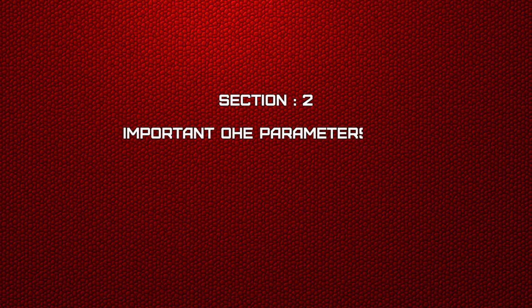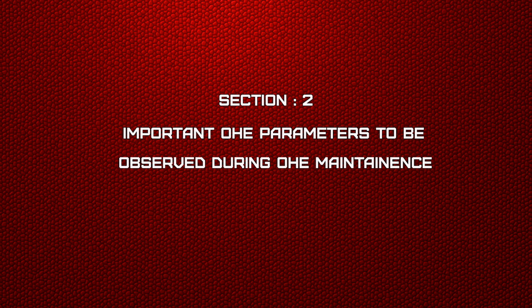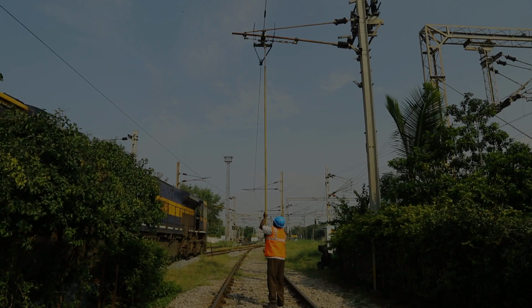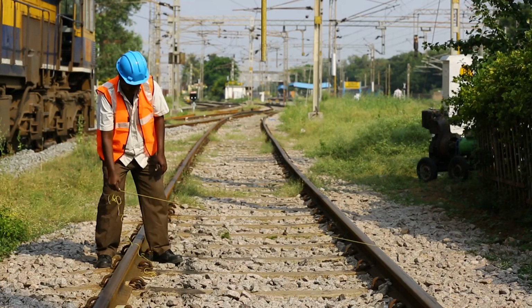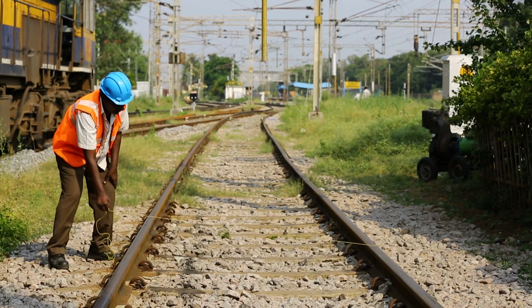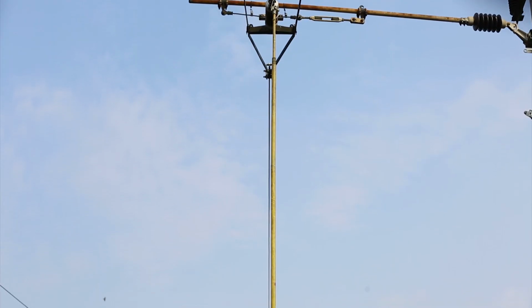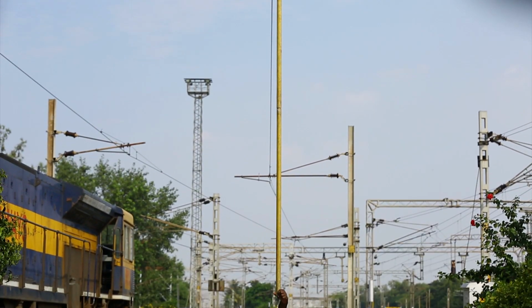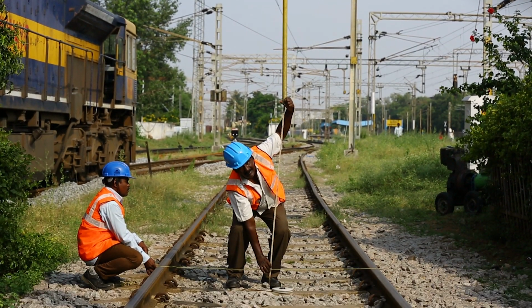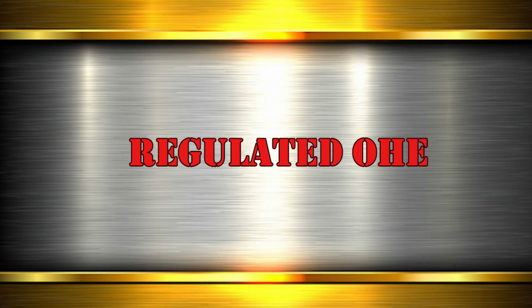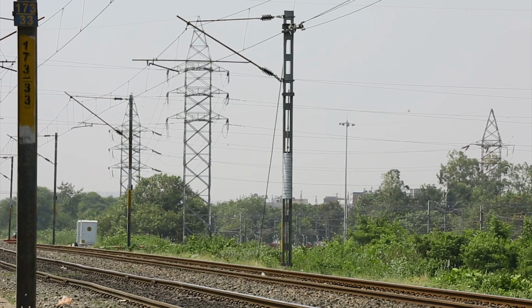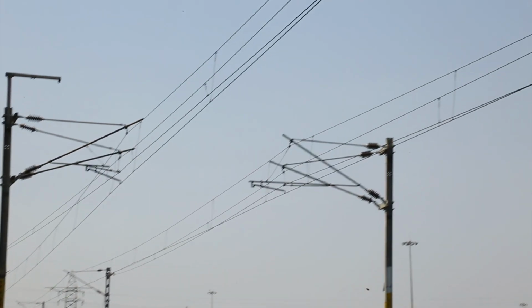Section 2. Important OHE parameters to be observed during OHE maintenance. Contact wire height. It is measured from rail level. Operating rod, fiber tape, and plumb bob are used for measuring contact wire height. Regulated OHE. It is the arrangement in which the OHE is stretched in between two ATD, auto-tensioning devices, on both sides of termination.